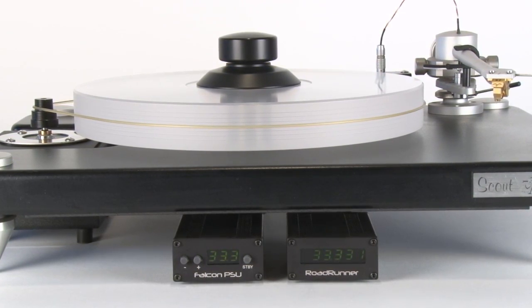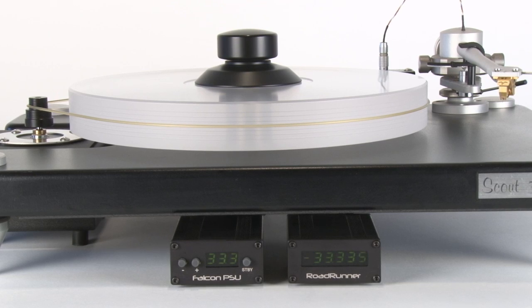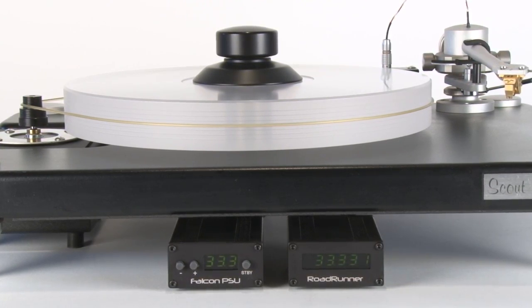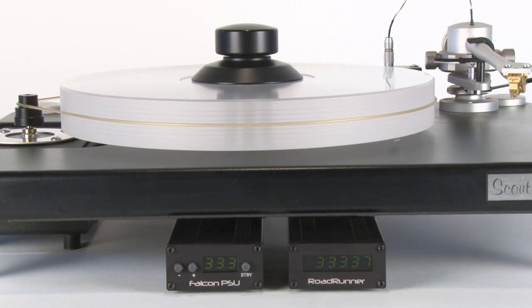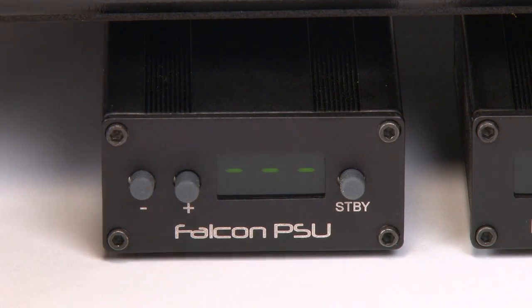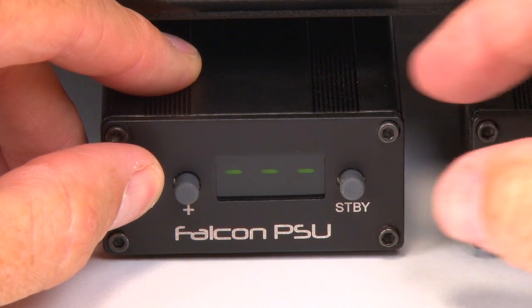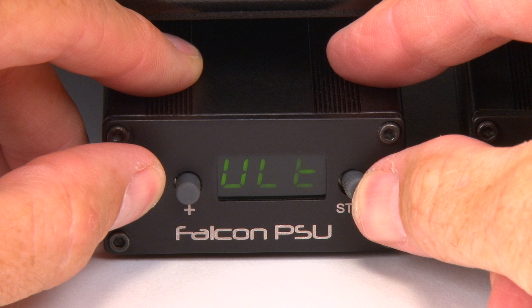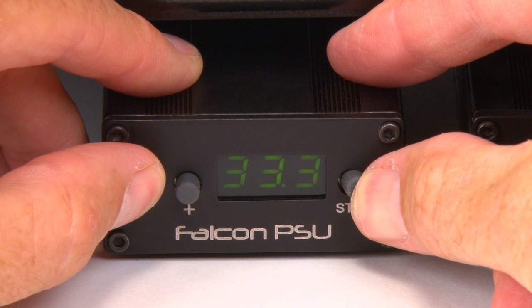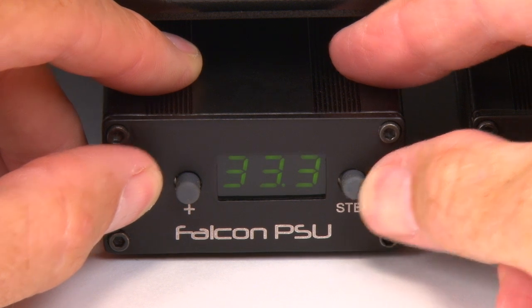Voltage output mode has separate adjustments for 33 and 45 RPM. Both can be selected, displayed, and adjusted while in voltage output mode. Enter voltage output mode from standby mode by holding the minus button. Press and release the standby button. The display will show VLT to indicate voltage output mode. The display will briefly show the current speed, then display the reduced output voltage for that speed selection.